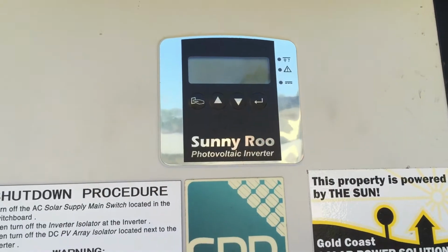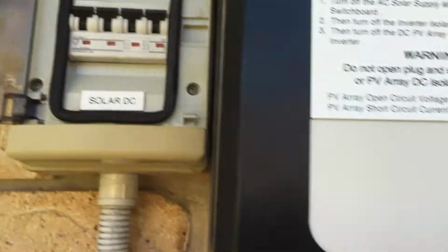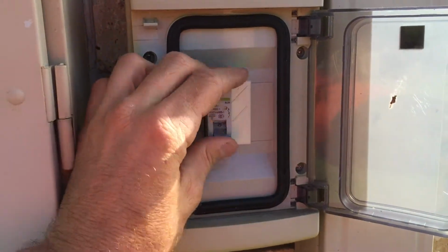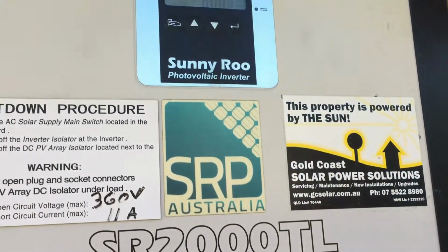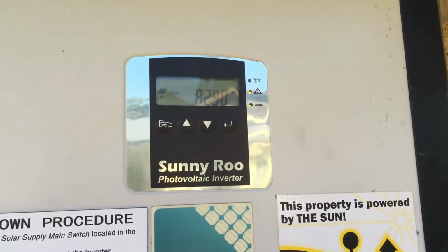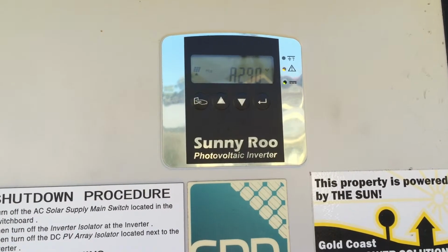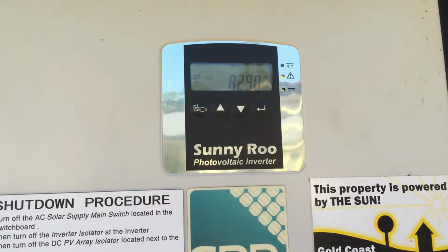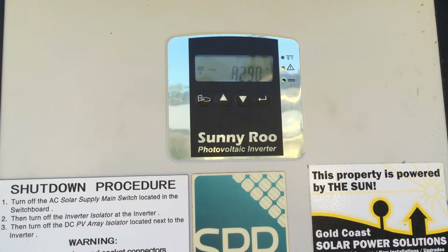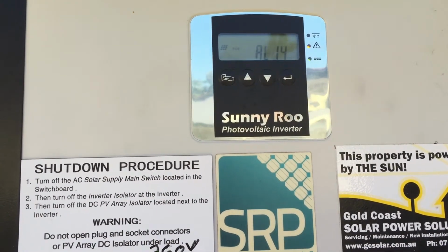So we'll go turn it back on now. So we'll just reverse the process, turn it back on, so DC on first, then down to the AC on, and we'll see what the inverter has to tell us from that. So it's still coming up with AL14 at the moment, but that should try and reconnect again there. So like I said, the AL14 error means that there's a problem with the utility. It's seeing a problem with the utility.